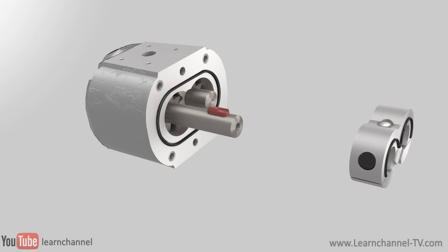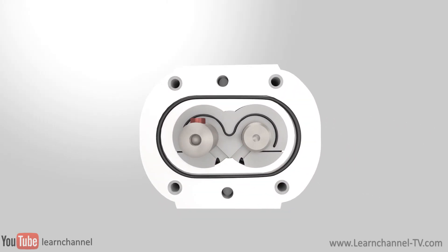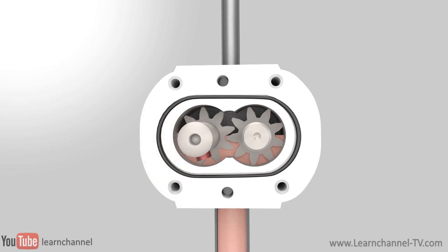Let's mount the parts together once more and watch how the pump works. When the wheels rotate, the tooth gap is closed by the opposite tooth, but when a tooth emerges from the gap, negative pressure occurs. The bigger the teeth and the higher the pressure, the pulsation of the pressure at the outlet of the pump gets worse.